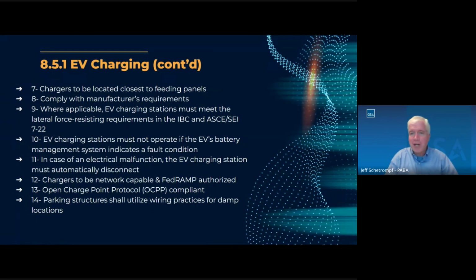Number eight, all chargers should be installed per manufacturer's recommendations. Again, something that seems pretty self-evident and shouldn't have to dwell too much on, but just be aware that there may be internal dip switch settings, maybe some jumpers in there. We need to make sure that all that's gone through during activation. If we stay with the default settings, we may not be getting what we thought we were getting.